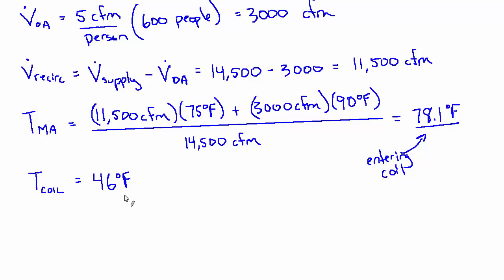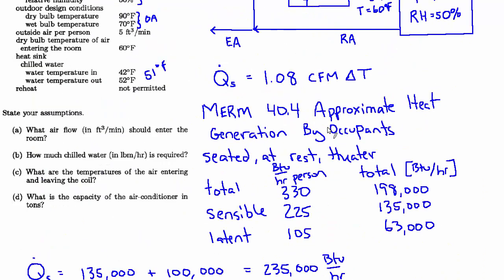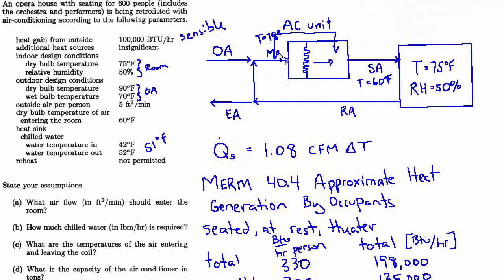Of course, that air is too cold. You don't want to supply 46 degree air. So you mix it after the coil with the mixed air that bypassed the coil, which is 78 degrees. And you take some portion of 46 degree air and 78 degree air, mix them together.